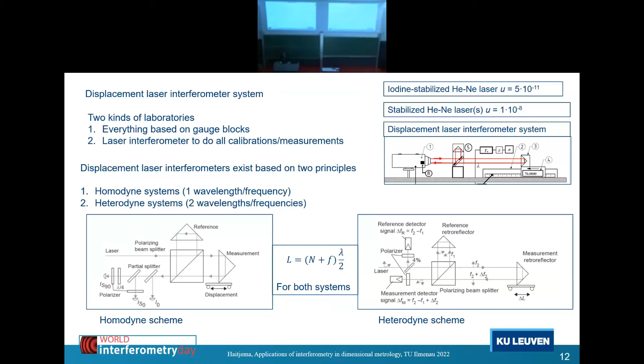But they both work. And to look a bit into what the sensitive factors are, I have here the display of one of the types, and you can see here the length in millimeters. You see here the resolution in nanometers. You see here what has to be input: the expansion coefficient, the air pressure, the air temperature, the relative humidity, and also the temperature of the thing you're measuring. It can be an instrument, it can be material. And in the end, out of this computer, you hope it does it okay. It's a kind of effective wavelength, and you will recognize it's about the wavelength of the red helium neon laser. So that's how it works.